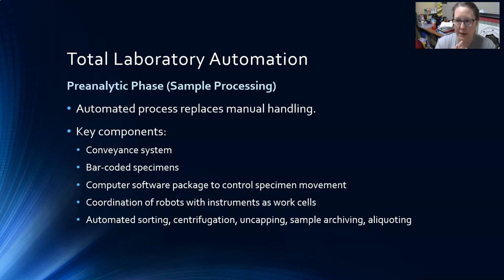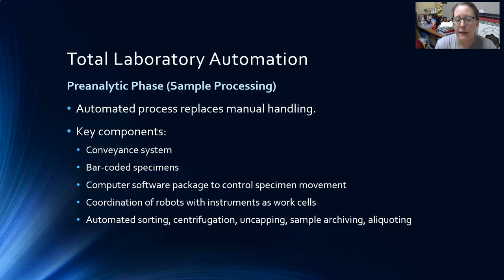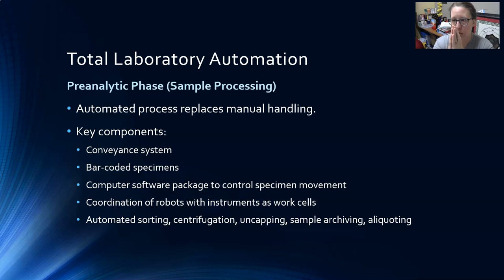Everything that needs centrifugation goes to centrifugation automatically. If it needs to be uncapped to be loaded on the analyzer, the machine uncaps it — not a lab tech. If a specimen needs to be split between two analyzers, the system can pull off part of the specimen into another tube, which is automatically barcoded and tracked. So one specimen becomes two specimens going in different directions.